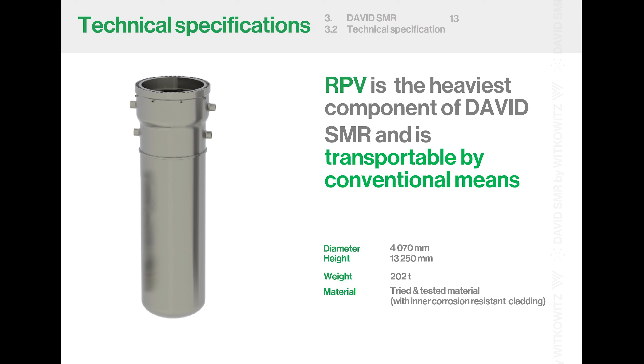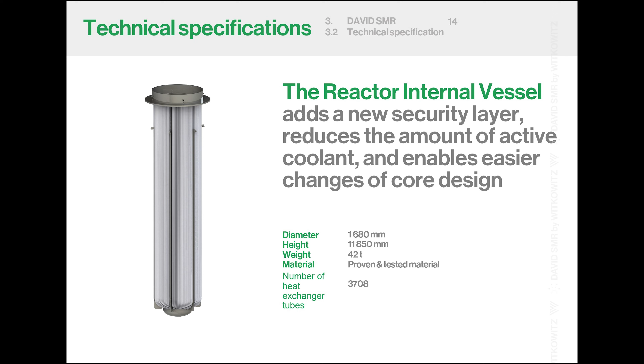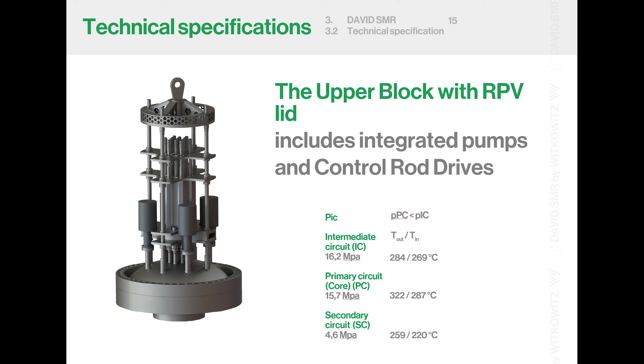The reactor internal vessel adds a new security layer. It's a complicated heat exchanger, but in nature it's similar to a steam generator, therefore it is a known design. The upper block can actually keep higher pressure in the intermediate circuit than in the primary circuit, by design. This allows us to have a high concentration of boric acid in the intermediate circuit. This means that in case of a leak, the medium with high boric acid concentration will be pushed into the inside of the reactor, stopping the fission reaction.